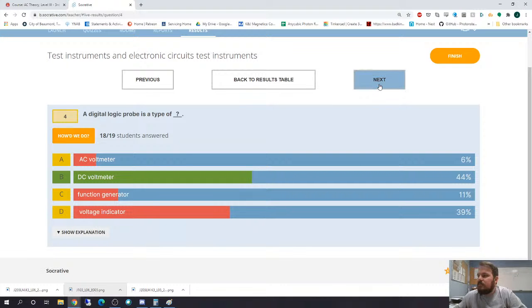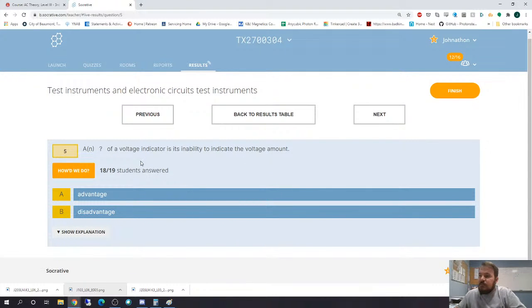A disadvantage of a voltage indicator is its inability to indicate the voltage amount. Voltage indicators, since they can't tell you how much voltage there is, just tell you whether there is voltage or not. It won't give you very accurate readings because you don't know if it's just trace voltages, like 5 volts or less, or if it's 500 volts, because it's just beeping.